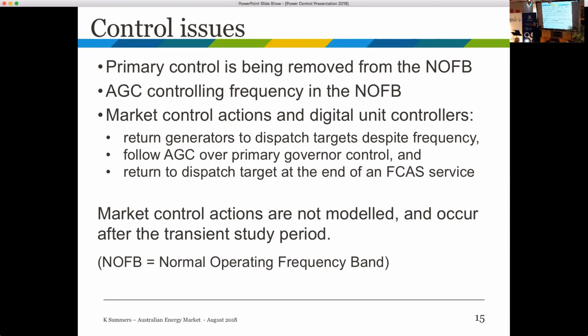They follow the AGC, which is the FCAS regulation target, over their primary governor control. So if the AGC, a 15-second time-delayed signal, says go down, even though the governor is trying to go up, they will go down because the market says so. They'll only give the service they were enabled for in the market, because that's what they're getting paid for, and then they go back to their dispatch target.